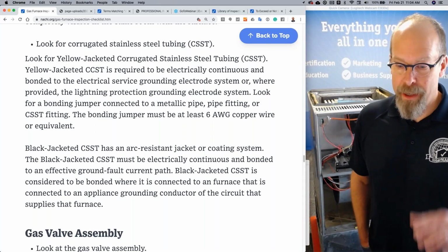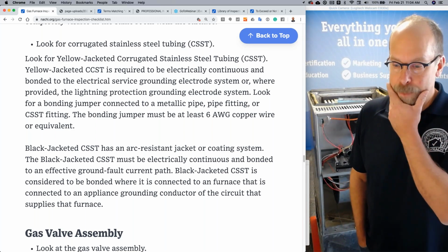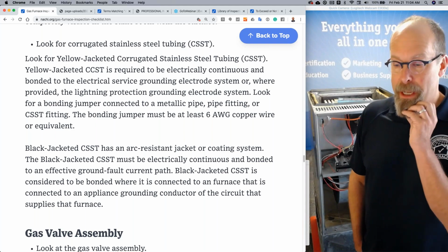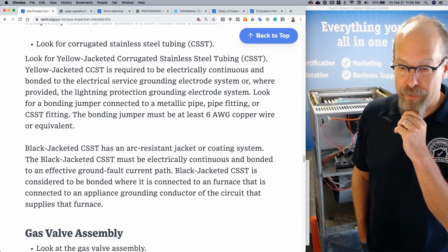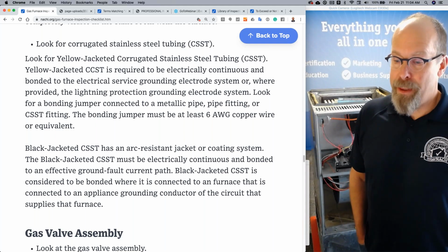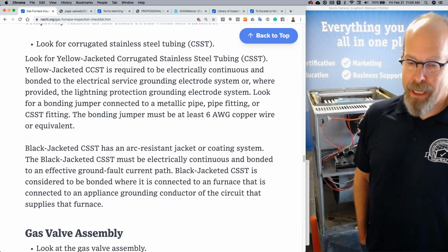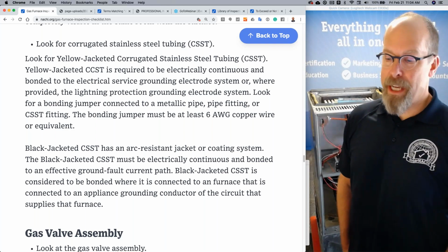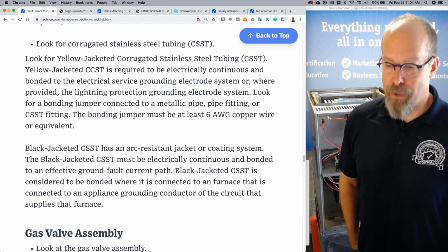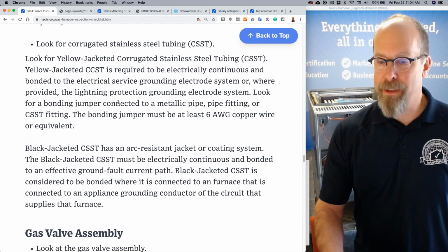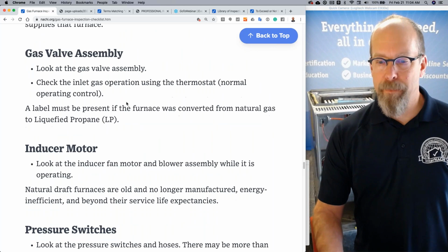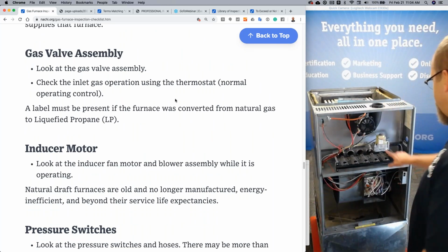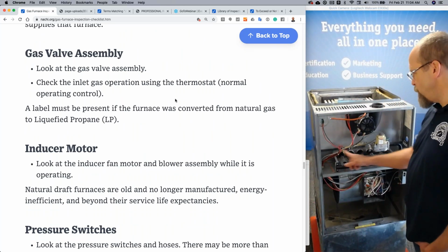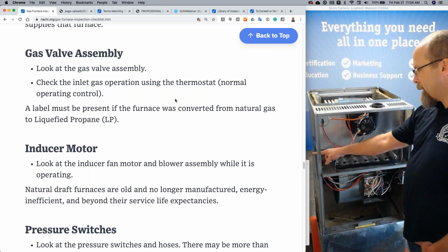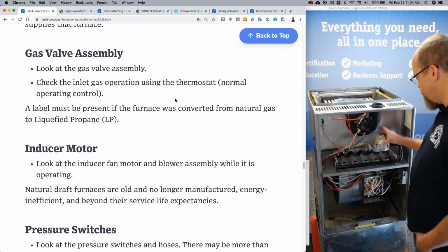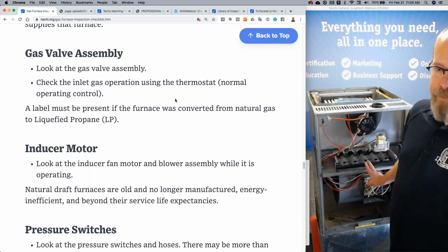The black jacketed CSST must be electrically continuous and bonded to an effective ground fault current path. The black jacketed CSST is considered to be bonded where it's connected to a furnace that's connected to an appliance grounding conductor of the circuit that supplies electricity to the furnace. Gas valve assembly, it's this one. So I removed the solid black gas pipe, right? And here's the gas assembly manifold.